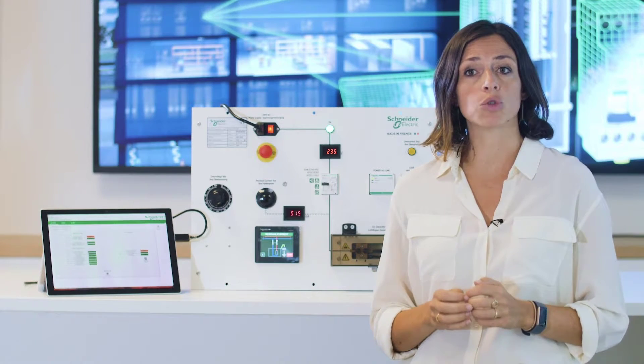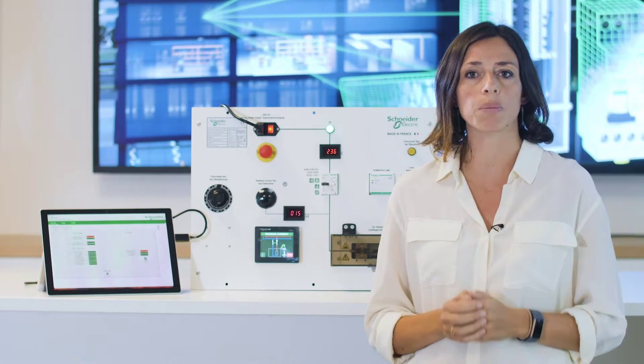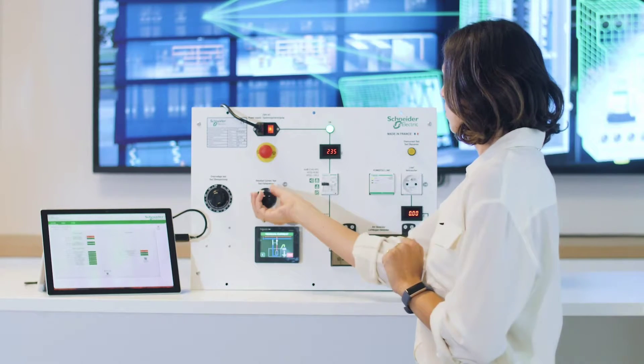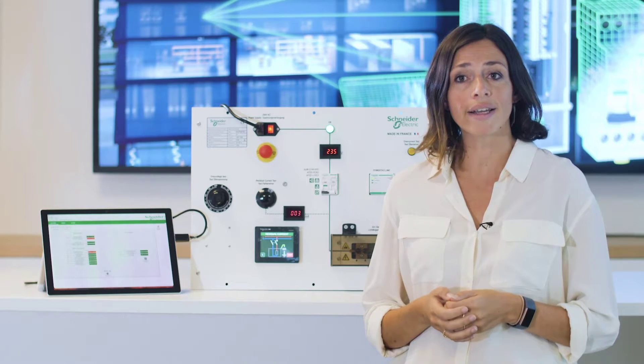You still have time to perform preventive or corrective actions to avoid the power disruption. If I don't take action and I continue to increase the leakage current, the product is tripping. Now I get an alarm.